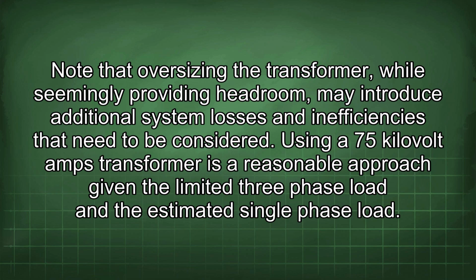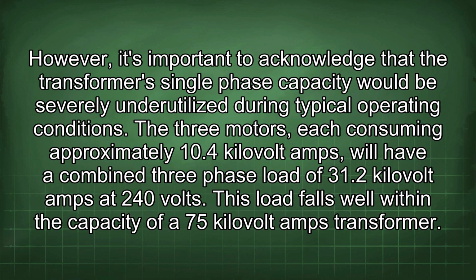considered. Using a 75 kVA transformer is a reasonable approach given the limited three-phase load and the estimated single-phase load. However, it's important to acknowledge that the transformer's single-phase capacity would be severely underutilized during typical operating conditions. The three motors, each consuming approximately 10.4 kVA, will have a combined three-phase load of 31.2 kVA at 240 volts. This load falls well within the capacity of a 75 kVA transformer.